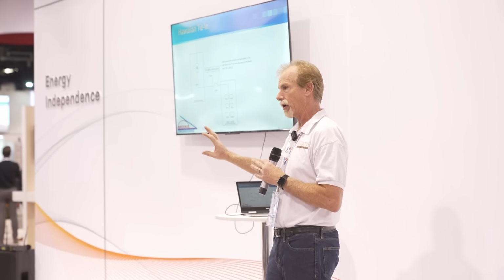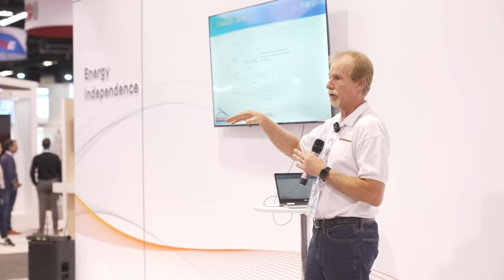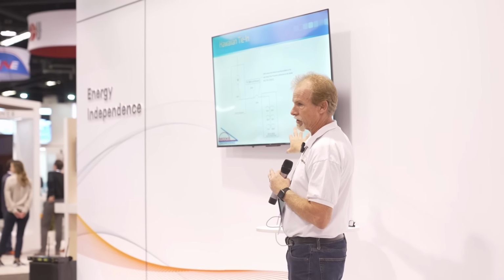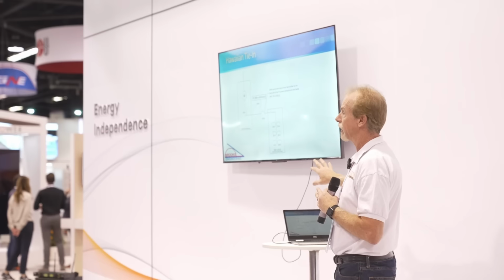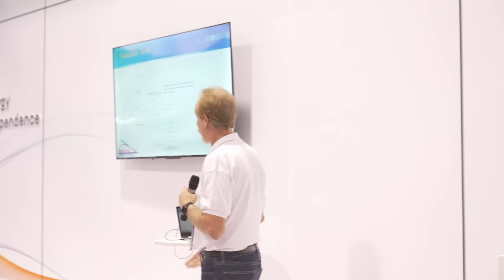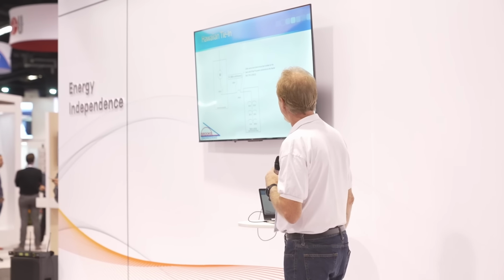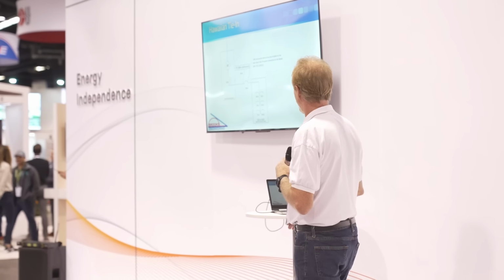So I said, okay, well, let's just tie in right after that 100 amp breaker, put another 100 amp breaker downstream of that, and you can go all the way up to 100 amps all day long. There are literally thousands and thousands of these systems in Hawaii set up just like that. And we can go as large as we want. So everybody said, well, anything over 40 amps on a 200 amp service, I have to do a supply side connection. That is absolutely wrong. It's never been true, but it's certainly not true right now. And we've always had this kind of option to do that.